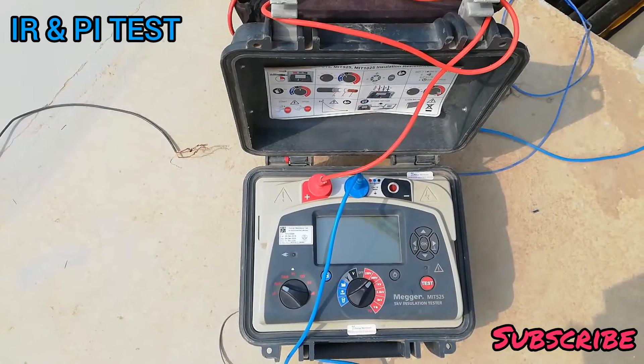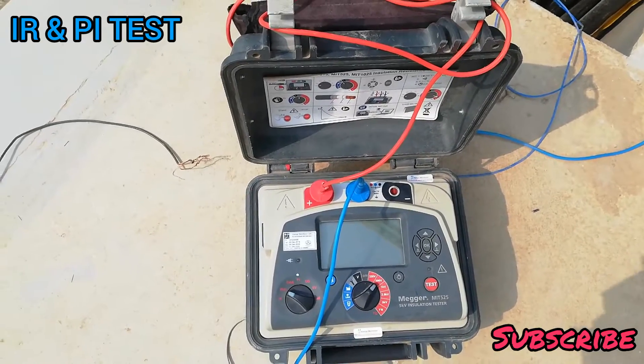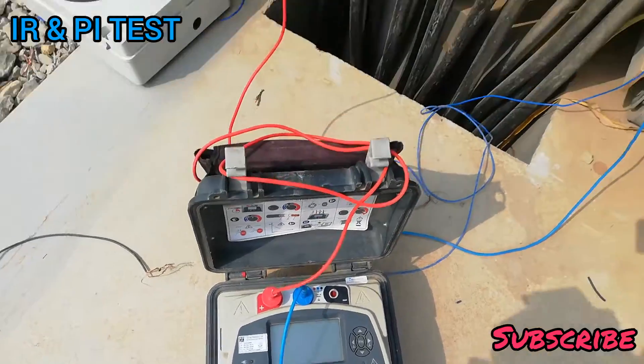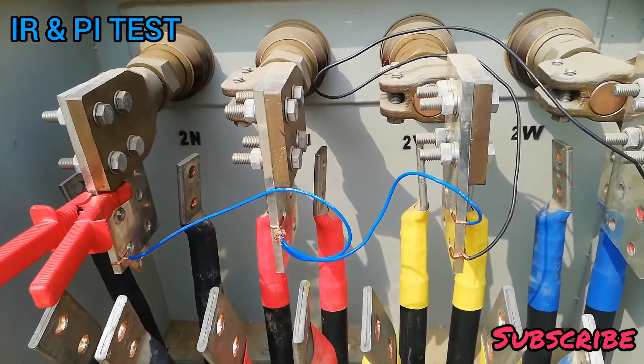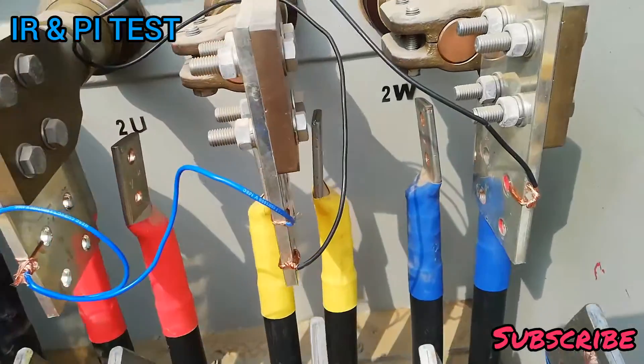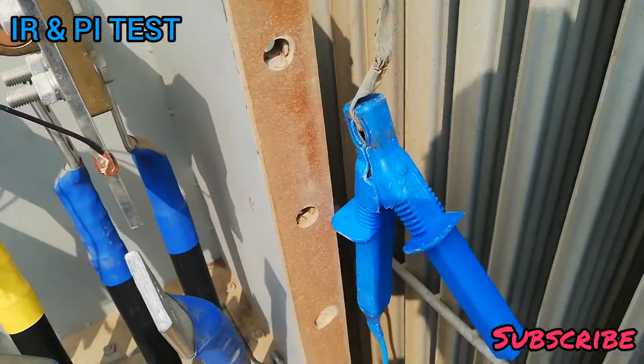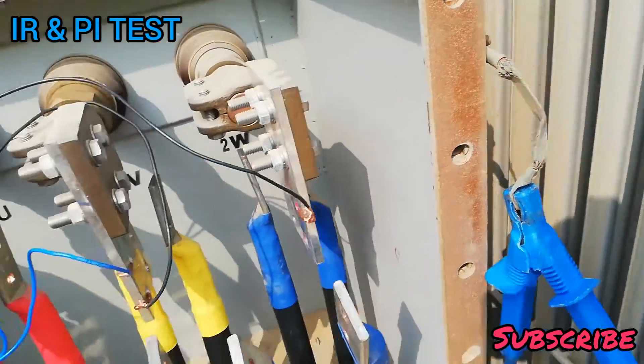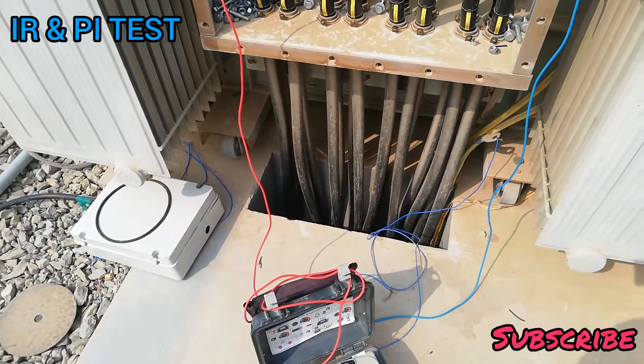We will start with insulation resistance and polarization index testing of the transformer. This is a Megger IR tester — it injects DC voltage. We will check insulation between the low voltage side, which will be shorted, and connect the red lead. The blue lead will be connected to the earth of the tank.